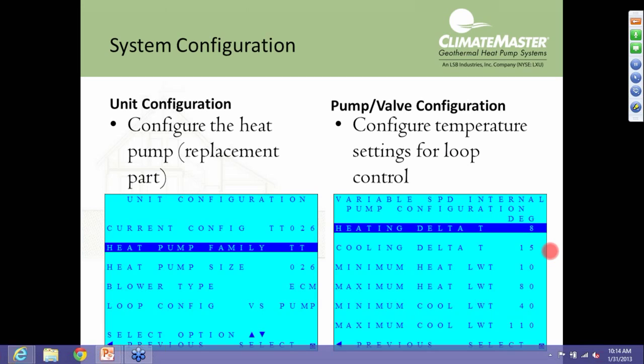And then under loop configuration, you'll have your variable speed pump. You'll have variable speed pump in parallel. Again, variable speed pump in parallel will be if we have multiple units on a common loop. We've got to choose variable speed pumps in parallel because the pumps are in parallel with one another, and we've got to control that pump a little bit differently. It's kind of an arm wrestling match between those pumps so that one doesn't lose out and flow stops and then the unit locks out.